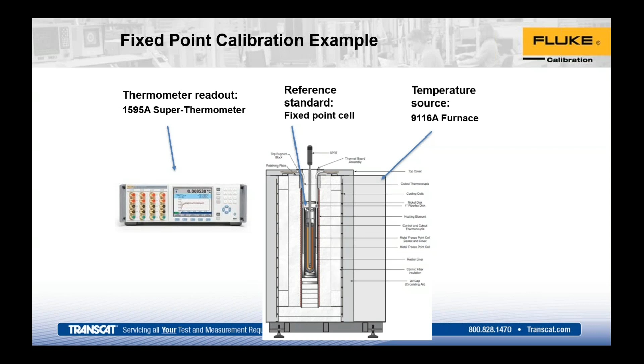With the fixed point process, you can achieve very, very low uncertainties in the cell. Some of them are as low as 0.15 millikelvin. So when you hear that, that's 0.00015, which is what you can achieve in some of the fixed points. So it's very good to start the calibration chain, or what they call traceability.